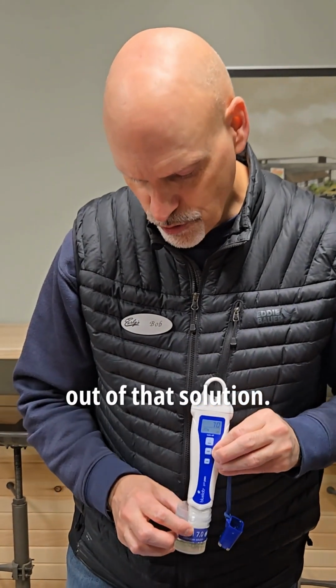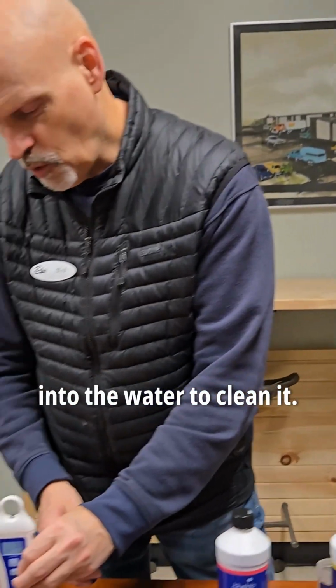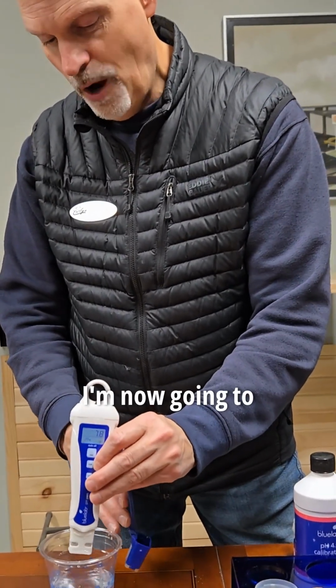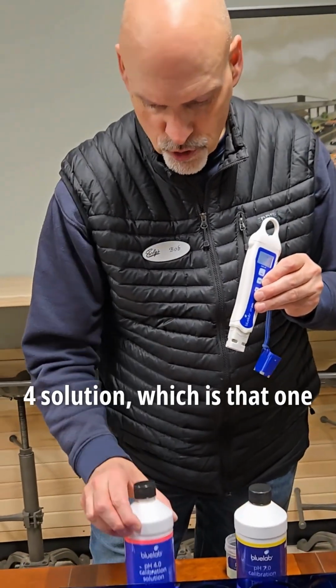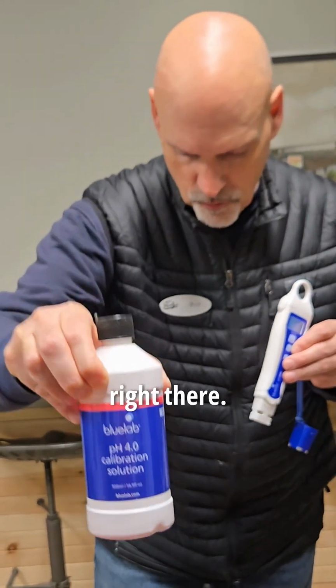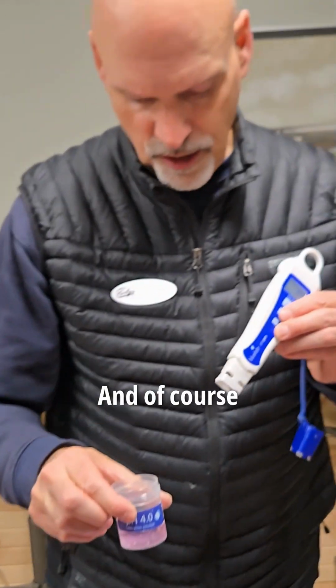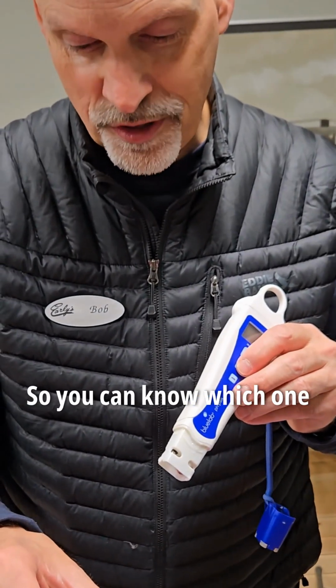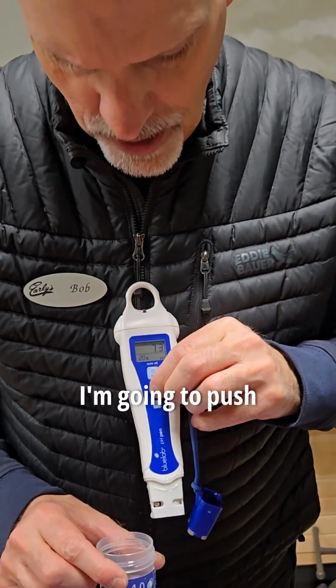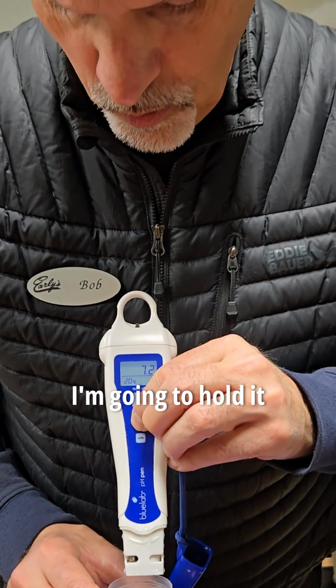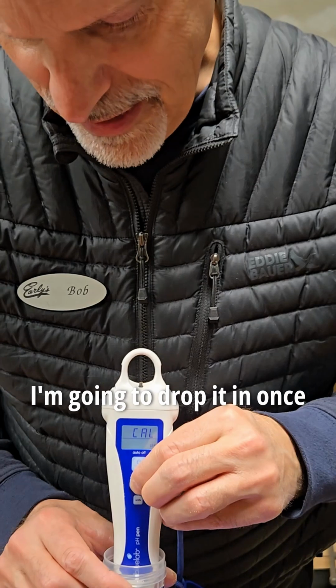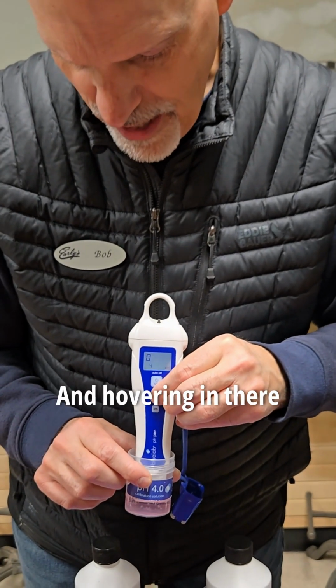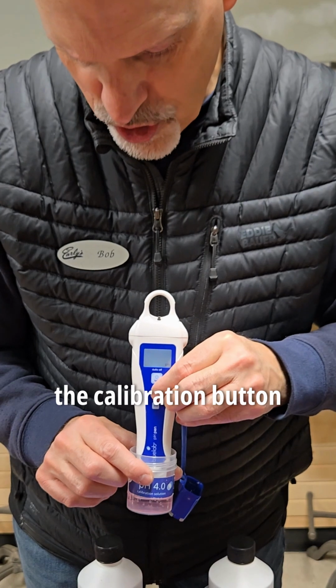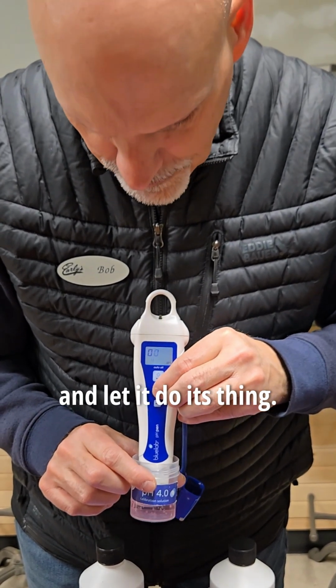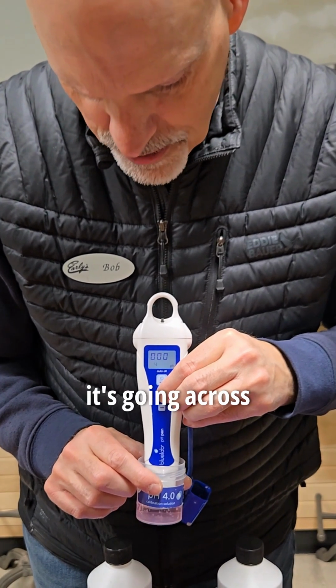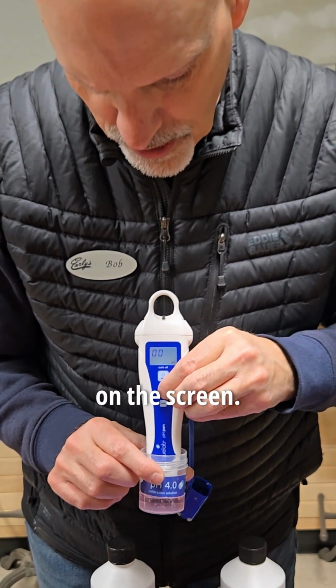I want to take it out of that solution and dip it back into the water to clean it. I'm now going to pick up my pH 4 solution, which is that one right there. And of course it is a different color, so you can know which one is 7 and which one is 4. And again, I'm going to push the calibration button and hold it until it says cal. I'm going to drop it in. Once it's in the solution and hovering in there, I'm going to release the calibration button and let it do its thing. And you can see the zeros are going across the screen.